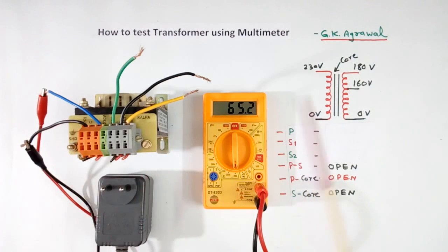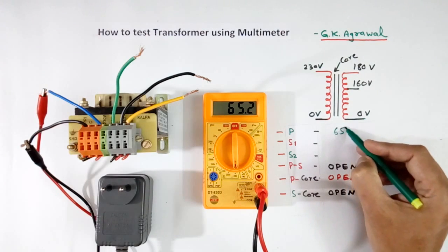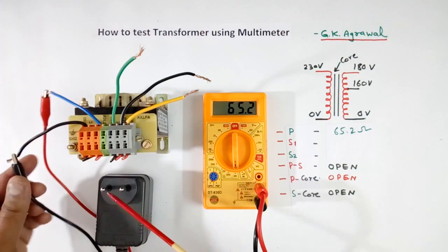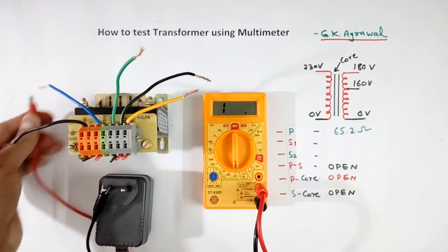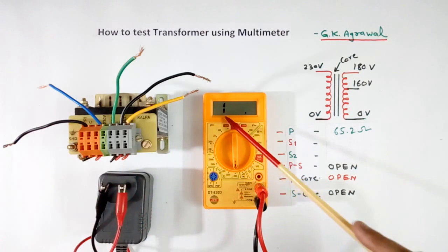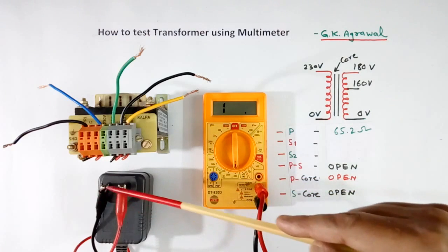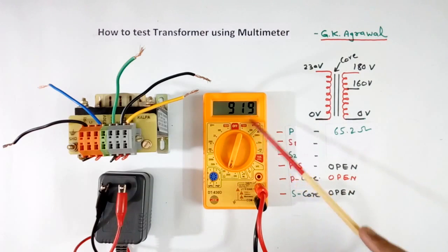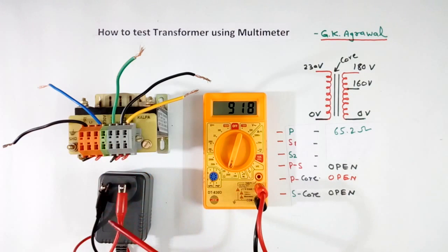Now I have connected my multimeter across the primary. It is showing 65.2 ohm — not showing 0, it is showing some value. So I will write 65.2 ohm. Now I have another small transformer. I will check the primary winding resistance of this also. Now this is showing open, but open doesn't mean it is bad. I had set the scale to 200 ohm, so I will increase the scale. Now it is showing 919 ohm. This value is much higher because this transformer is of small rating — about 10 VA.